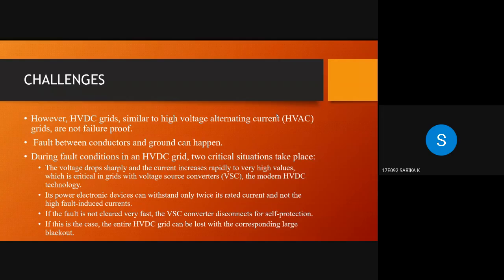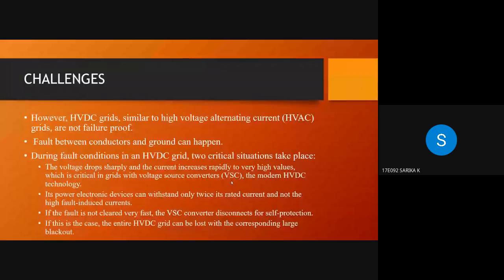During fault conditions in an HVDC grid, two critical situations take place. The voltage drops sharply and the current increases rapidly to very high values, which is critical in grids with voltage source converters, the modern HVDC technology. Its power electronic devices can withstand only twice the rated current and not the high fault induced currents. If the fault is not cleared very fast, the VSC converter needs protection. If this is the case, the entire HVDC grid can be lost with the corresponding large blackout.